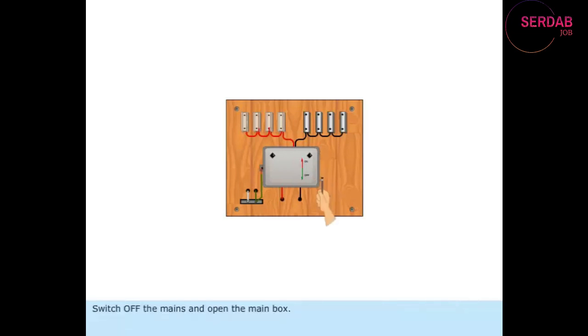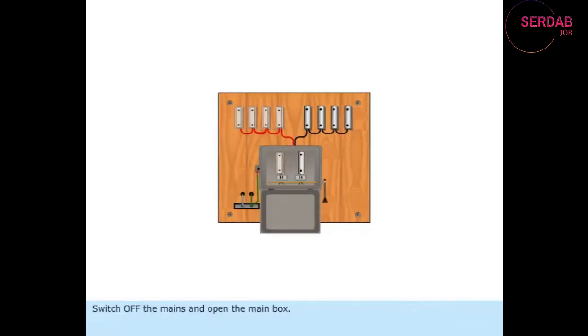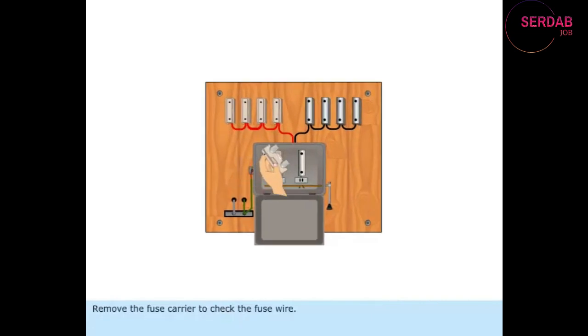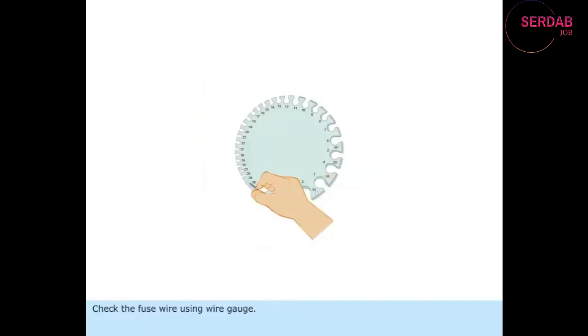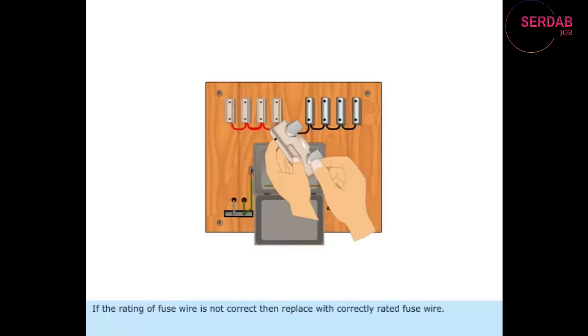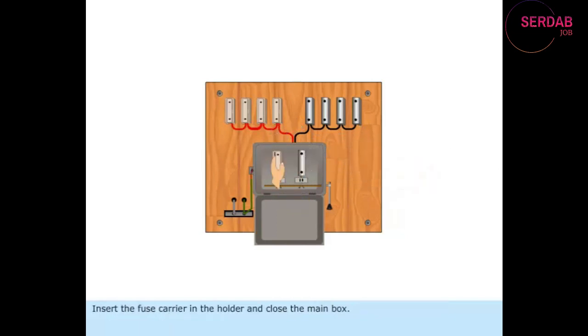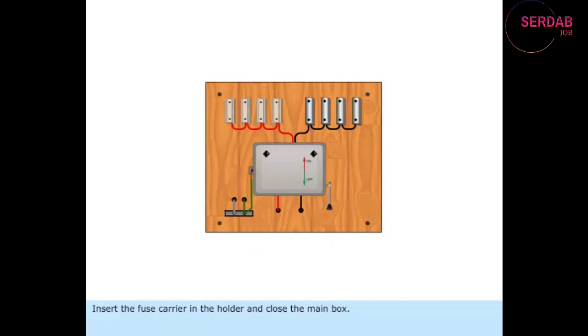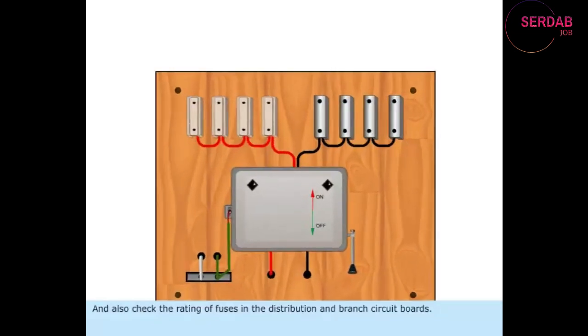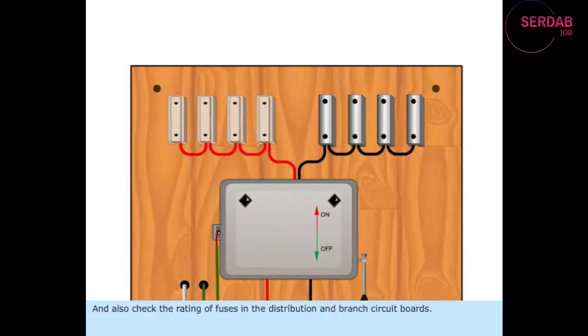Switch off the mains and open the main box. Remove the fuse carrier to check the fuse wire. Check the fuse wire using wire gauge. If the rating of fuse wire is not correct, then replace with correctly rated fuse wire. Insert the fuse carrier in the holder and close the main box. And also check the rating of fuses in the distribution and branch circuit boards.